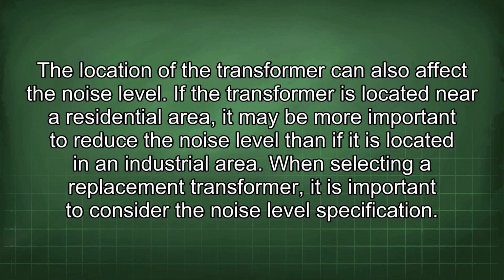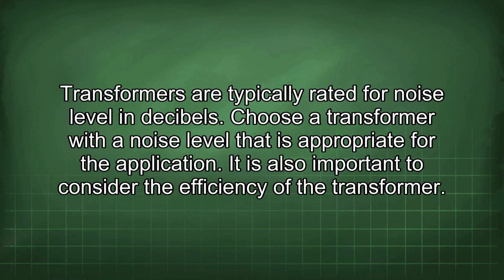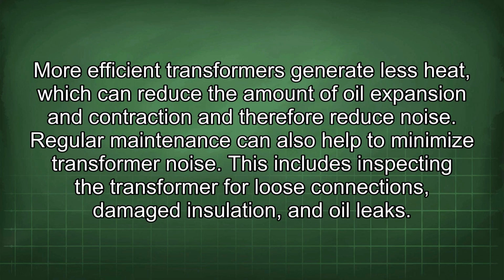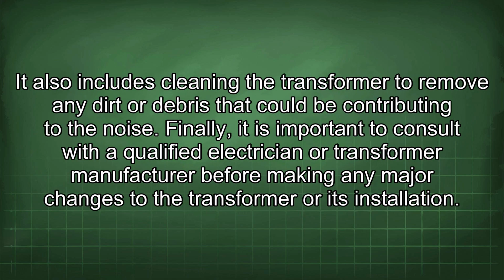When selecting a replacement transformer, it is important to consider the noise level specification. Transformers are typically rated for noise level in decibels. Choose a transformer with a noise level that is appropriate for the application. It is also important to consider the efficiency of the transformer. More efficient transformers generate less heat, which can reduce the amount of oil expansion and contraction and therefore reduce noise. Regular maintenance can also help to minimize transformer noise. This includes inspecting the transformer for loose connections, damaged insulation, and oil leaks. It also includes cleaning the transformer to remove any dirt or debris that could be contributing to the noise.